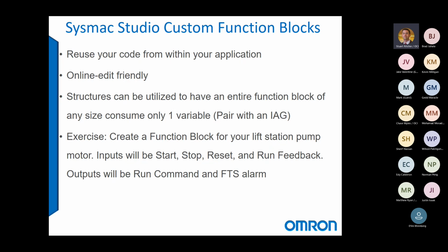Another point, this is a very nice feature. Our function blocks can be online edited. Not entirely, but most of it can be online edited. So you often don't need to shut your plant down if you've got a bunch of function blocks and you had to make a change to them. Now we can combine structures and function blocks to really simplify our programming. We can use structures in our function blocks. We can use structures on our HMI as an IAG. If some of you hung around on the last session, we went over an IAG, how to create one and import it. So we can use the same structure in both places, and we can really expedite our programming that way.